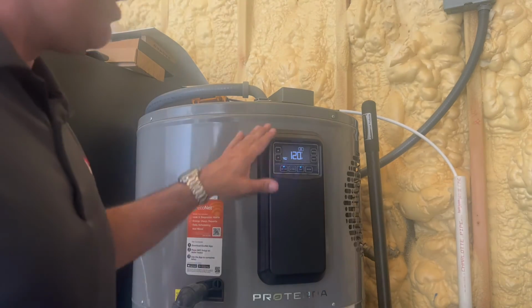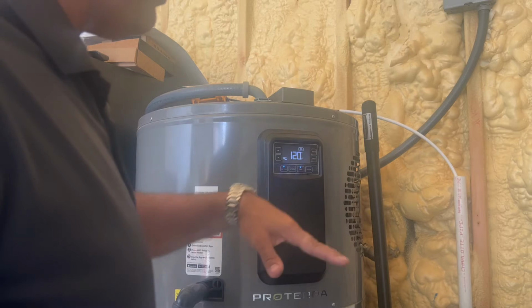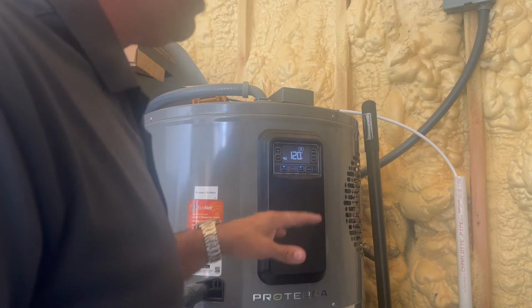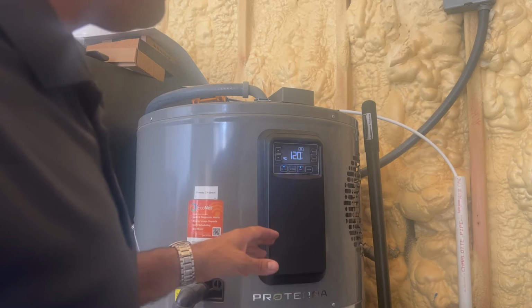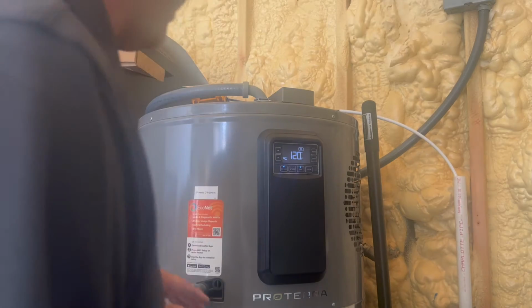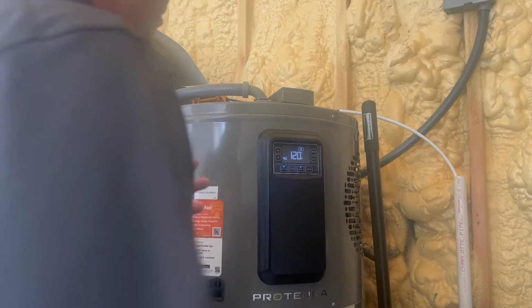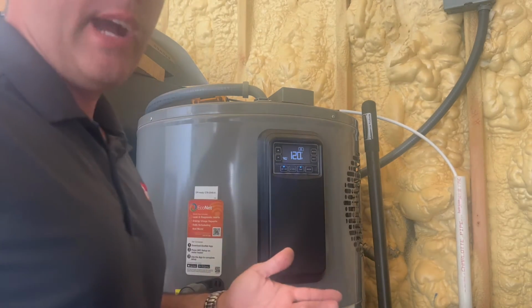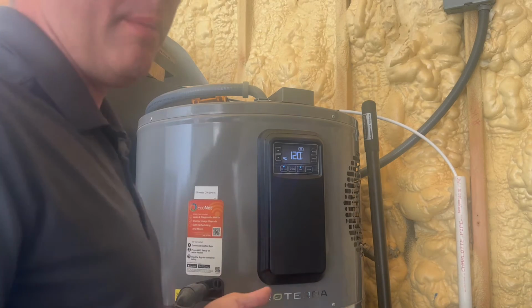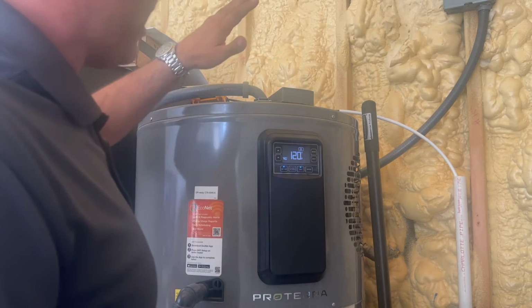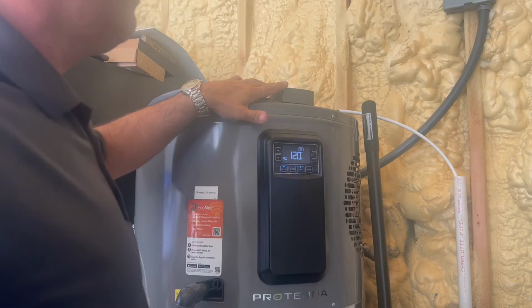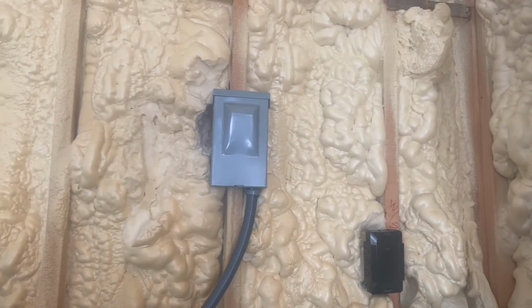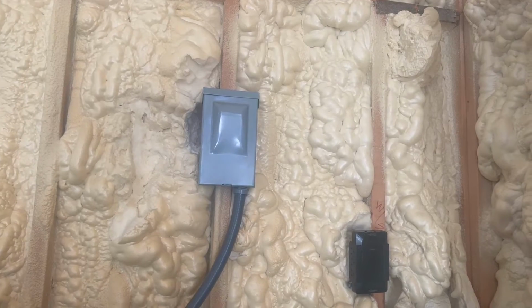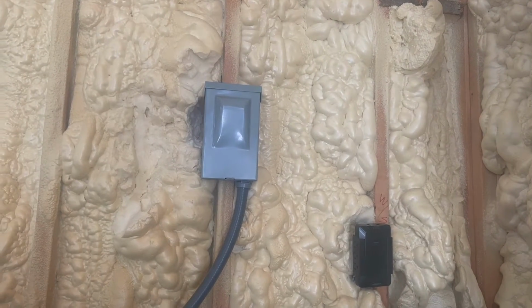Okay, now on our model here, we've got the screen lit up. It's showing that it's in a heat pump mode. Temperature set at 120. It's currently in standby mode. It's not calling for heat. But if you have a unit and you're needing to check the power, make sure you have proper voltage. A good place to do that is either at the top of the water heater or at your disconnect box. You can open up your disconnect box or the plug if it's plugged into the wall, and you can test right there.